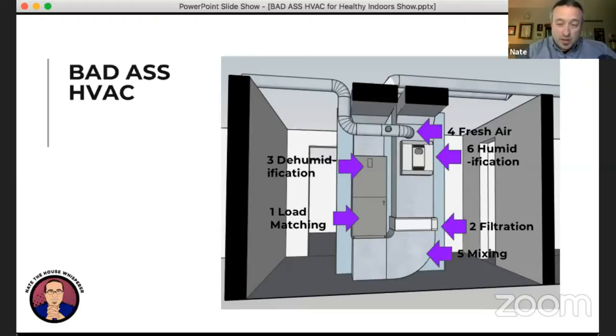So you see what that looks like, the bad ass HVAC. Note that the humidifier in this instance is on the return, so that's where the air is coming back into the system. That's a really big filter. What's nice about having that horizontal filter is you've got it in this huge duct, so the entire face gets hit, and because it's horizontal rather than vertical, the whole face gets hit evenly.